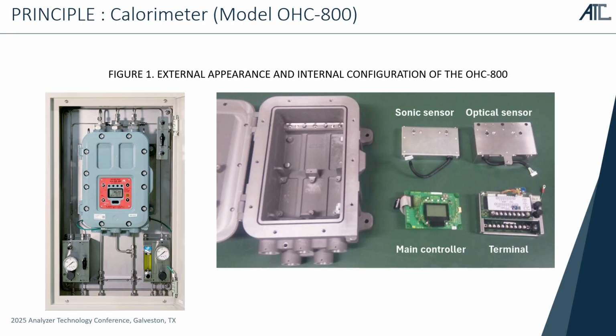Now I would like to talk about the calorimeter, the optosonic-based calorimeter. And the product name is OHC 800. As you can see on the left side, the enclosure has a sampling system, which is for two lines, one line for the sampling gas, the other line for the reference gas. And then this is an explosion-proof unit. And then, as you can see in the right side picture, there are four modules installed in the enclosure.